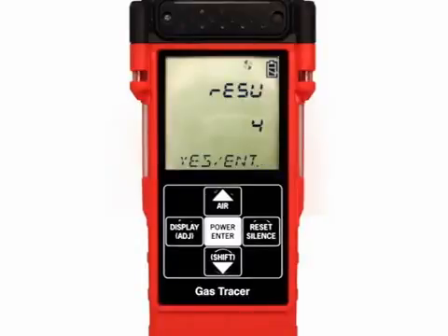If lunch break is turned on in maintenance mode, press and release the power enter button to continue accumulating time-weighted average, TWA, peak readings, and time in operation from the last time the gas tracer was used. The short-term exposure limit, STEL, reading is reset each time the gas tracer is turned on. Press and release the display adjust button to reset the accumulation of these measurements. If you do not press the power enter or display adjust button within 5 seconds, the gas tracer automatically resumes accumulating the TWA peak readings and time in operation.